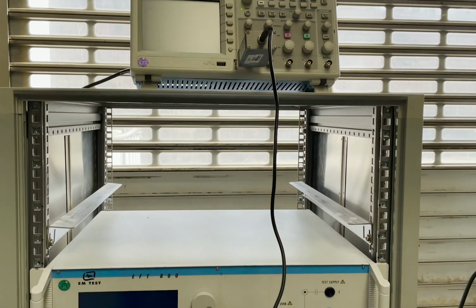The electromagnetic compatibility lab is where the international standard tests are carried out. We have the equipment for the main EMC immunity and emissions test. We test the burst with increased voltage up to 7 kV and the surge until 10 kV, with a second equipment capable of up to 100 kV available in the high voltage facility. Here we also test the frequency disturbances, emissions, immunity, voltage change, voltage fluctuations, magnetic and pulse magnetic field, an anechoic chamber for radiated signals, and more.